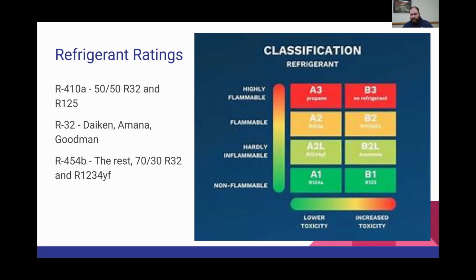We loved them. They were not toxic. They were non-flammable. You could burn them, just for the record, and burning any refrigerant, especially one that has chlorine in it, has the potential to create phosgene gas, which is super dangerous to breathe in. And so we've always had procedures in place to prevent us from burning refrigerants. We just overlooked them a lot as an industry. So we've had A1s, and with the push onto these HFO refrigerants we came out with new classification refrigerants. It wasn't an A1, but it met the technical requirements of an A2L.